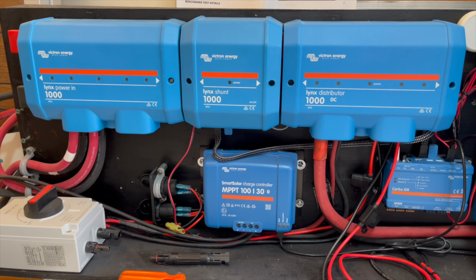My Victron Multiplus will, basically the maximum it will draw is about 200 amps. So definitely don't need a fuse bigger than 200 amps for each line. That would change depending on what the capacity is of your inverter. But in this case, it's 3,000 watts, or actually 3,000 VA, which is about 2,600 watts.